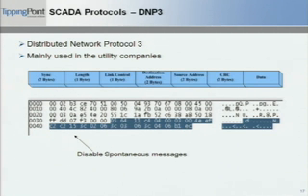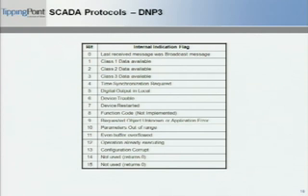But a funny thing happens in the DNP3 protocol: after every 16 bytes of data, a 2-byte CRC is added. And they have a different kind of CRC, called CRC DNP3, and I have that one implemented too, if someone requires it. It's kind of available outside too. And the next one is the link control, which ensures that your communication is going on fine, and then the destination address, source address, the CRC and the data. Here are some of the internal indication flags that DNP3 follows, which can be used against or in favor.